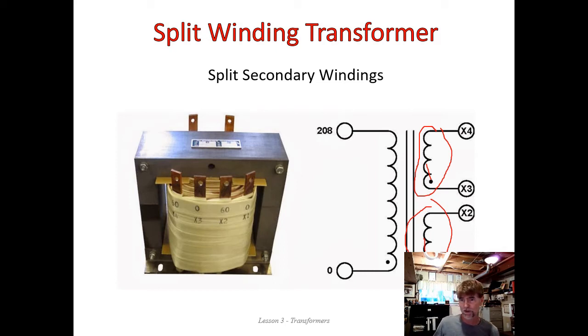The other thing that this slide shows us, and we'll see more of this in the next couple of slides to come, is some labeling. We haven't talked about any labeling yet, but notice that the secondary terminals are called X1, X2, X3, and X4. See, I just called it secondary, and in fact all of these slides assume that the primary is on the left and the secondary is on the right. The fact of the matter is, until we hook this up to a power supply and a load, we don't even know what the primary and the secondary is. But we can talk about high sides and low sides. And the X label represents the low side of the transformer. So if you actually hook this transformer up as a step up transformer, the X terminals would be your primary windings.